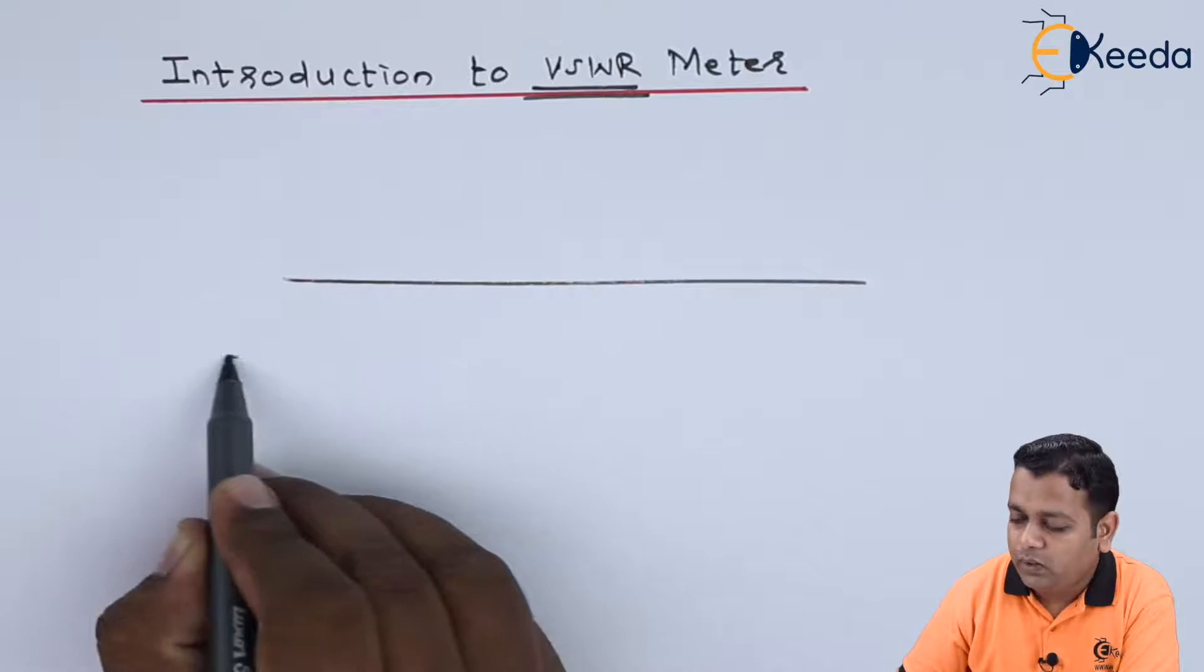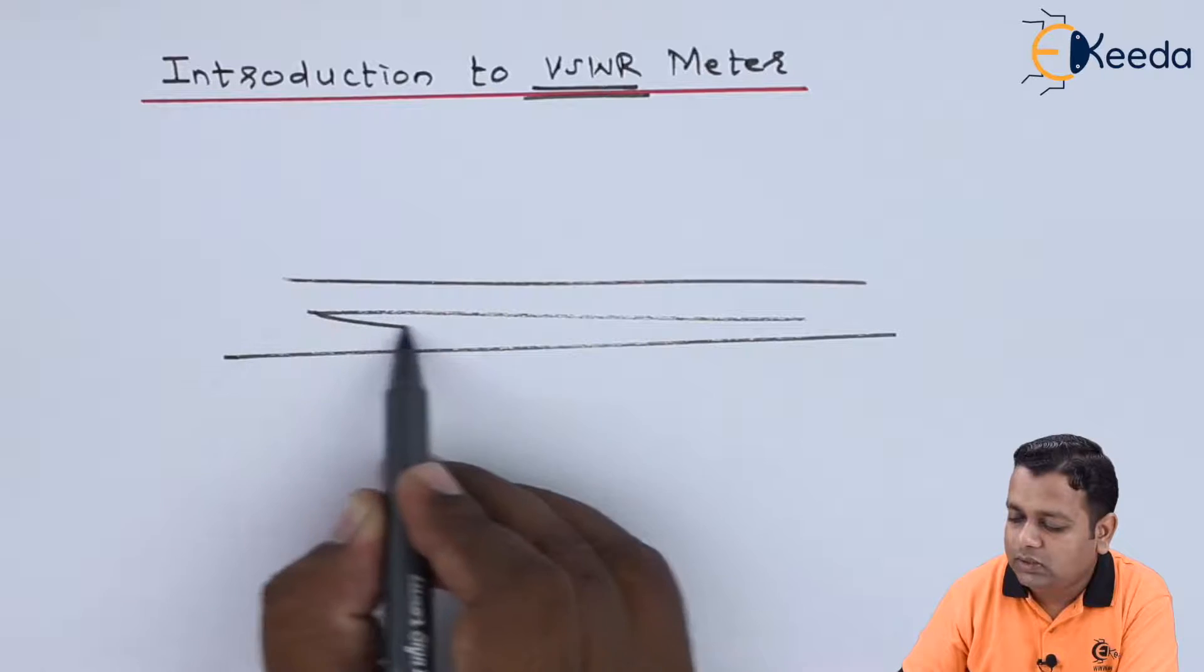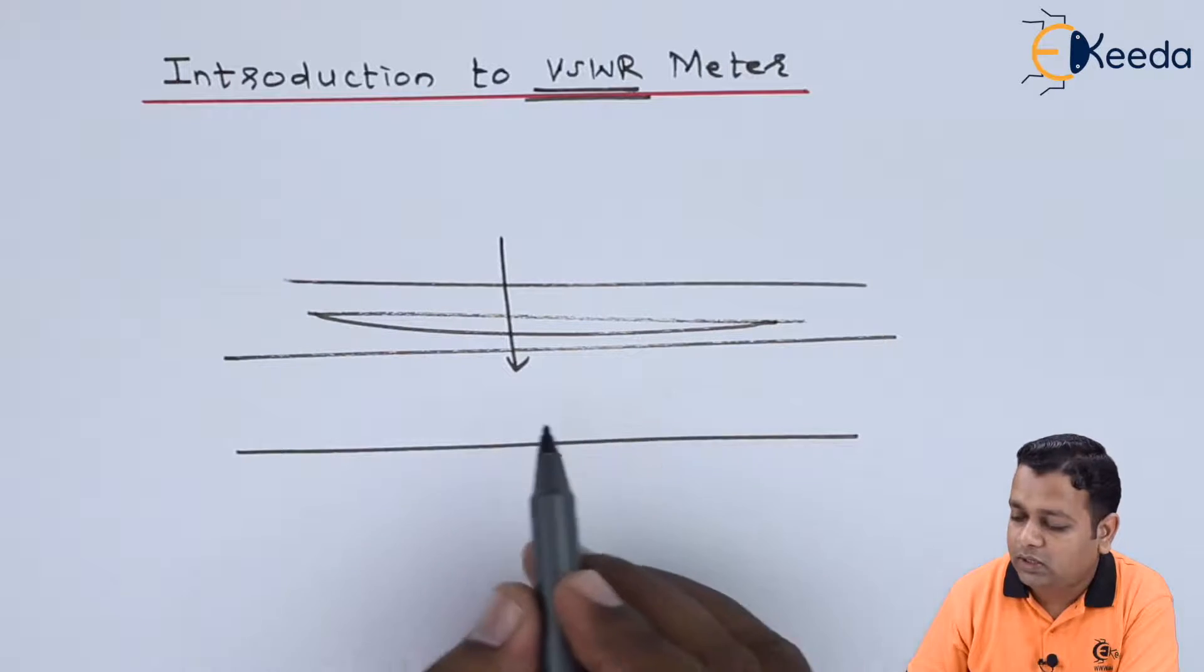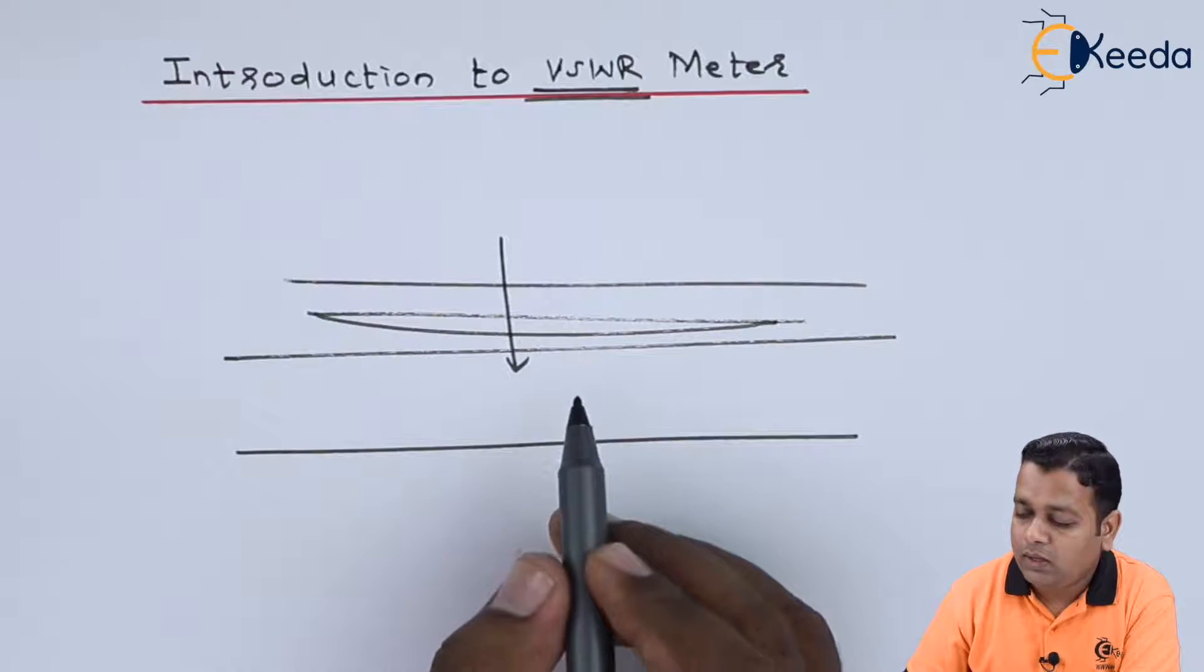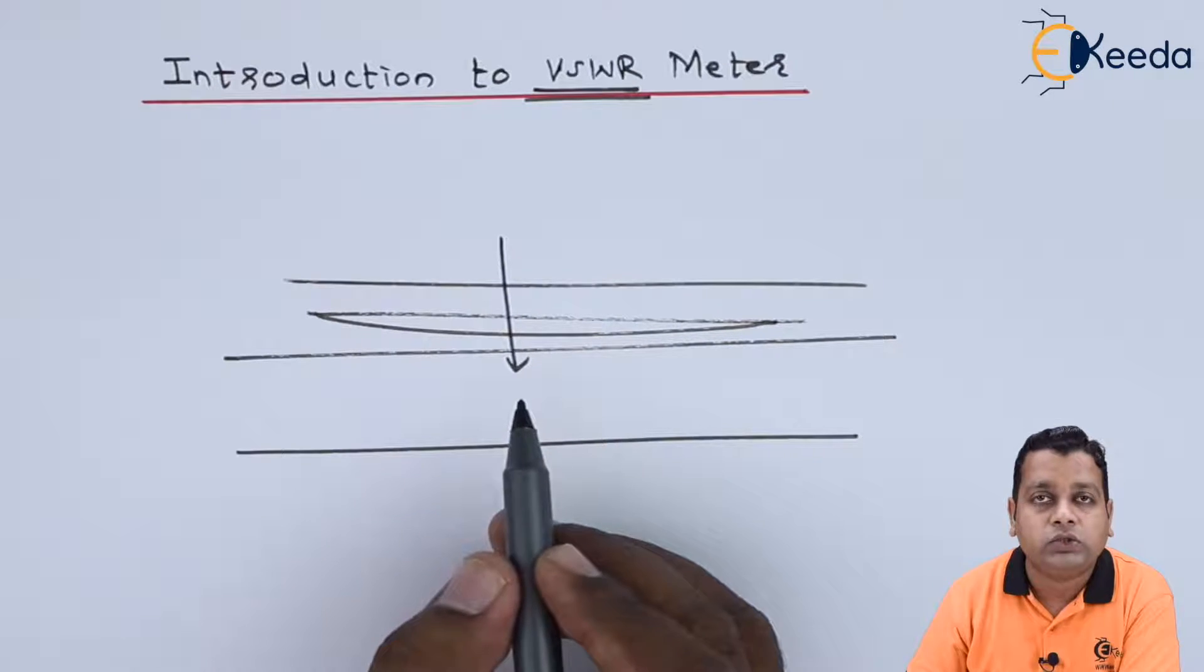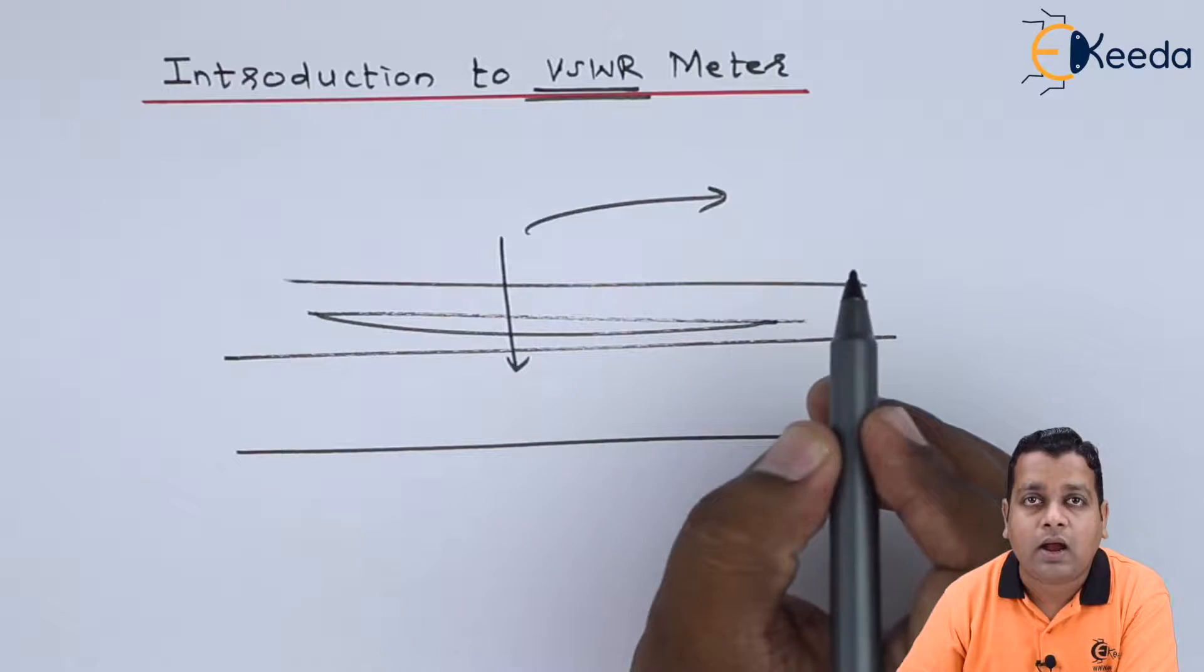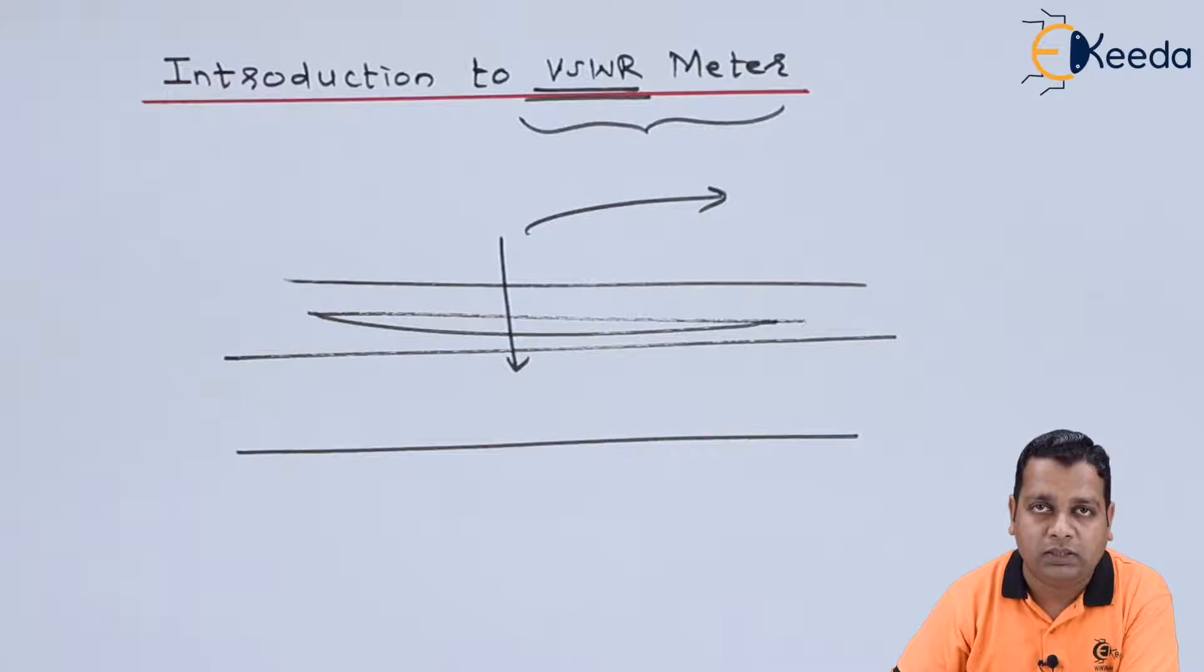Now basically when we have a waveguide, for practical case inside the waveguide we have such insertion slot and through this insertion slot we have the detector mount or the tunable detector sensor to measure the levels of voltages. Now while the sensor measures certain voltage level, whatever the output of that particular signal is there, it is further amplified, calibrated and provided as input to the VSWR meter.